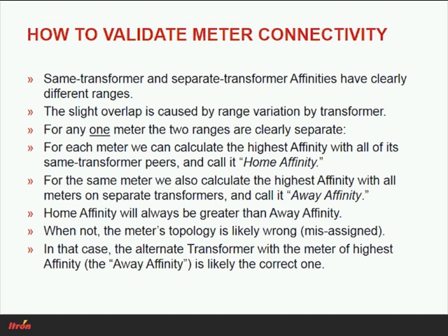So what we found with a lot of different tests is a good way to validate connectivity. Remember, the whole exercise here is to validate existing connectivity and correct it where it's found to be wrong. To validate it, we found the best way is to calculate, for each meter, the highest affinity with any of its peers.